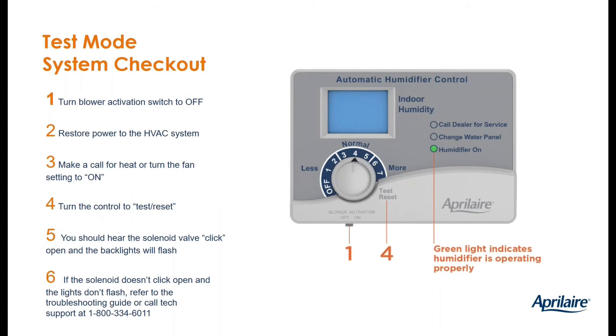Another really nice advantage of the automatic humidistat is the test mode. Test mode allows you, regardless of the relative humidity in the home, to run the humidifier for 1 minute. Test mode lets you run the humidifier for 60 seconds. So, turn the blower activation switch to off. That way we're testing the wiring between the HVAC system and the humidistat. Kick the power back on. I would say just make a heat call. Keep your life simple. Just make a heat call. Wait until you feel warm air coming out of the supply registers. Then go to the humidistat and turn it to test mode.